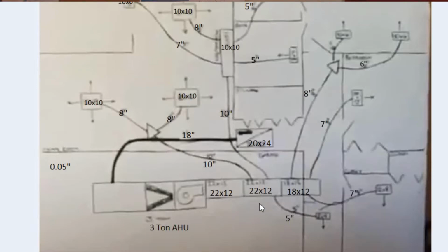But anyway, if you look at this, we've got some flexes coming off of a main trunk, feeding a triangular type of duct box, feeding more flex, going to what I'm assuming is a 10x10 ceiling diffuser here, here, and here. And then also up top here, we've got what might be a sidewall register. I really don't know. We don't know what this guy's doing. But we do know he's got one return right here in the hallway. We've got a central return, likely in the ceiling of this hallway, and a big 18-inch flex feeding that right there. Is this system going to work? Well, that's a good question.